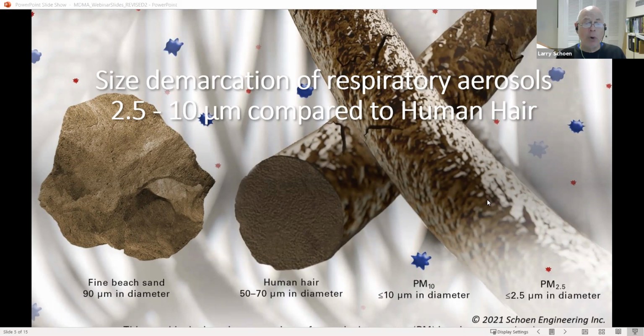Even though the virus itself is quite small, 0.1 microns, and the red dot here is 2.5 microns or smaller, so the virus is 1/25th of that, it never travels alone. It travels in the air as part of a mucus and salt droplet, frankly, because it's come from a person, it's come from the lungs. It's not traveling on its own, and we do have the ability to impact those particles with ordinary air filtration. You've probably heard MERV 13 mentioned a lot, but even filters down to the MERV 8 level do something in the particle size of interest. And the more you circulate that air through the filter, it repeatedly can do the particulate removal. So even if an infected person is in a room with other people who might be exposed, just by filtering that air within the room, we are reducing the risk to some extent. So keep that red size particle in mind.